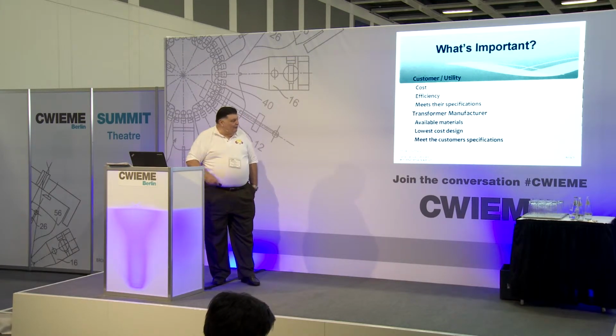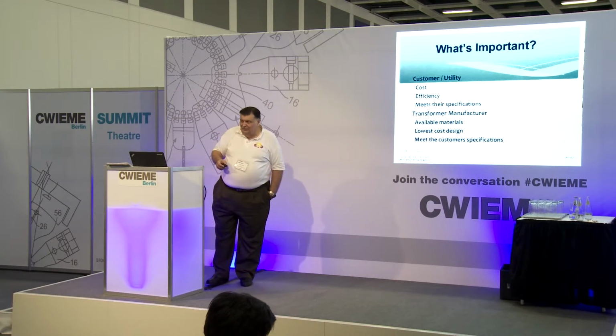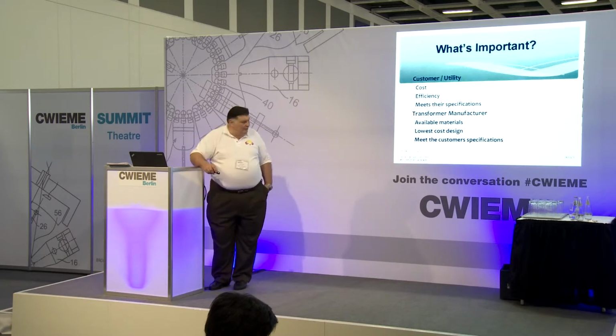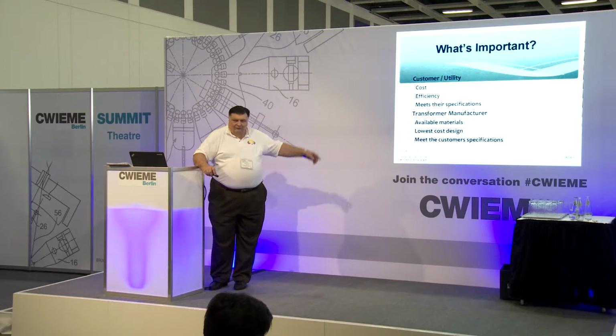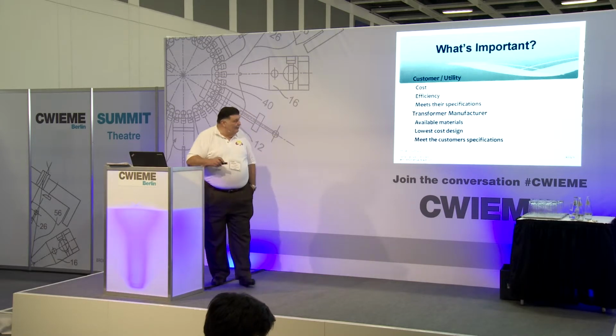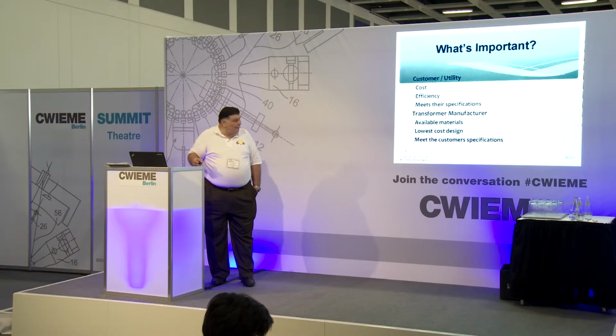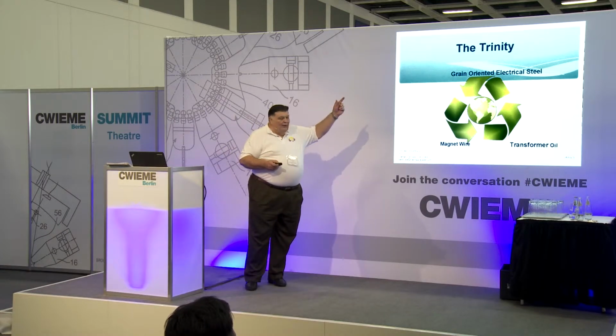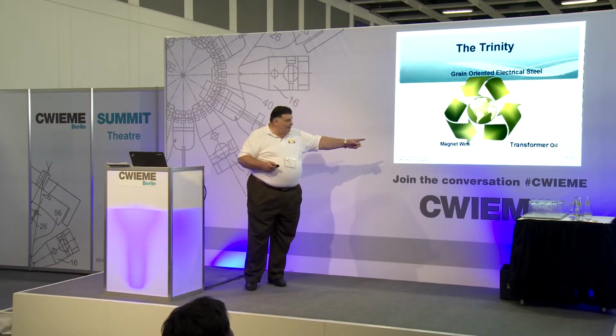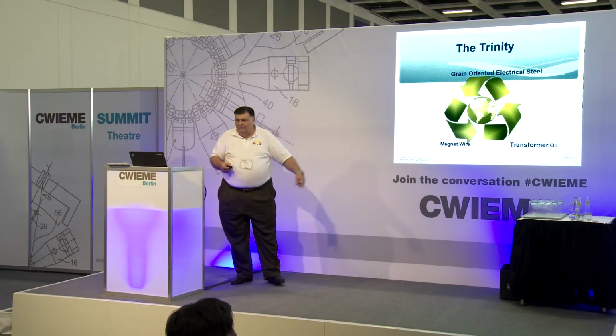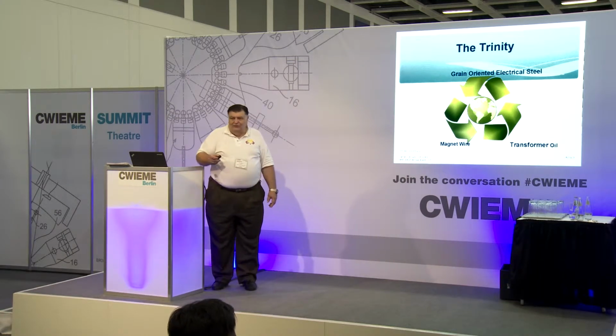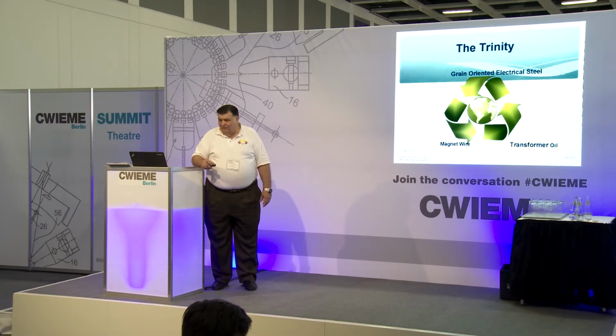The transformer manufacturer, what do they want? Availability of the correct materials, lowest cost design, and meeting customer specifications. And this gets to be a juggling act between lowest cost design and the availability of material. It's what I call the Trinity: grain-oriented electrical steel, magnet wire and conductor, and transformer oil. That's what you have to juggle in order to get the best design, lowest cost.